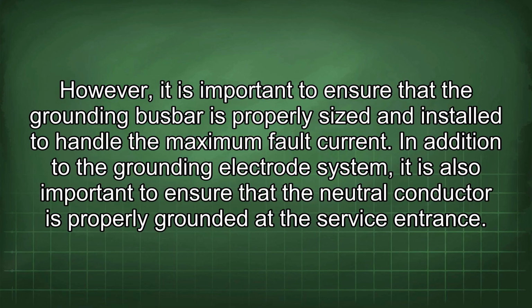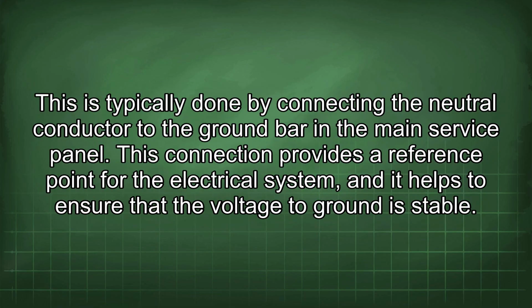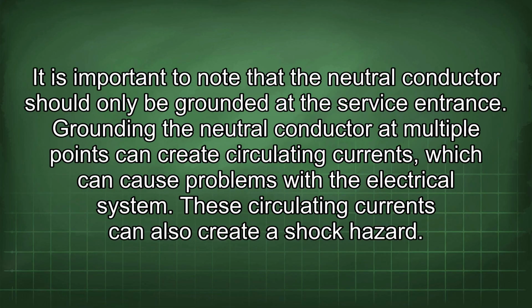current. In addition to the grounding electrode system, it is also important to ensure that the neutral conductor is properly grounded at the service entrance. This is typically done by connecting the neutral conductor to the ground bar in the main service panel. This connection provides a reference point for the electrical system, and it helps to ensure that the voltage to ground is stable. It is important to note that the neutral conductor should only be grounded at the service entrance. Grounding the neutral conductor at multiple points can create circulating currents, which can cause problems with the electrical system. These circulating currents can also create a shock hazard.